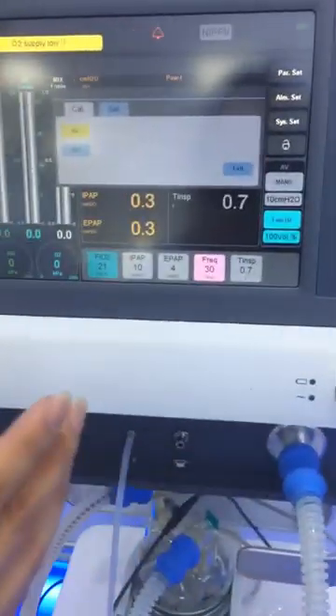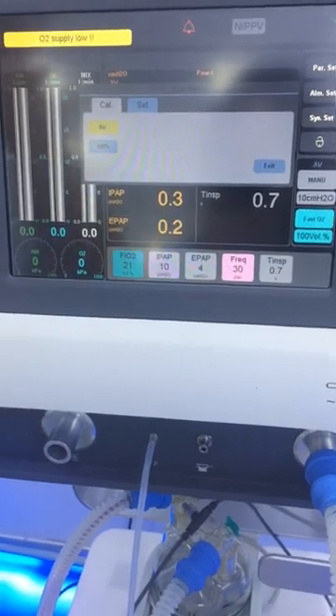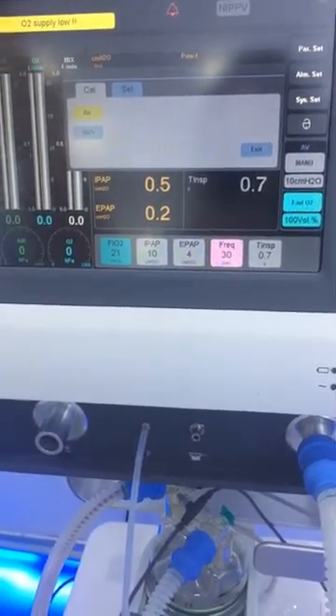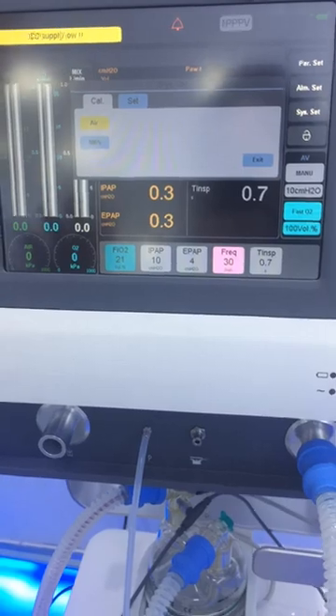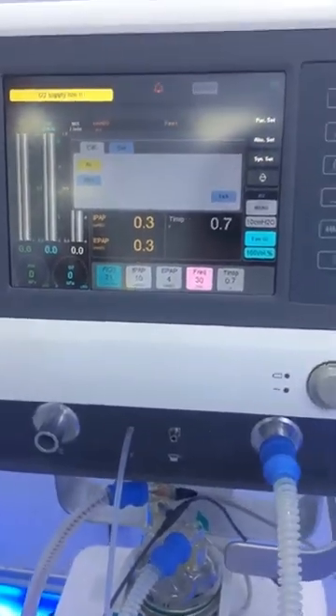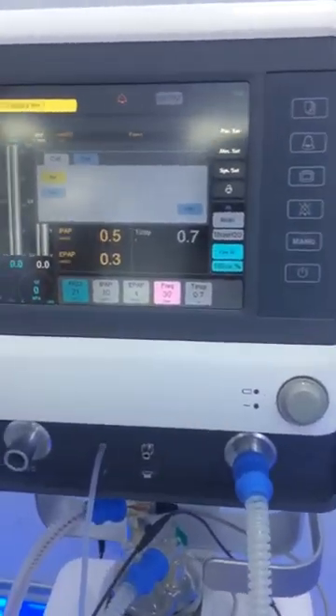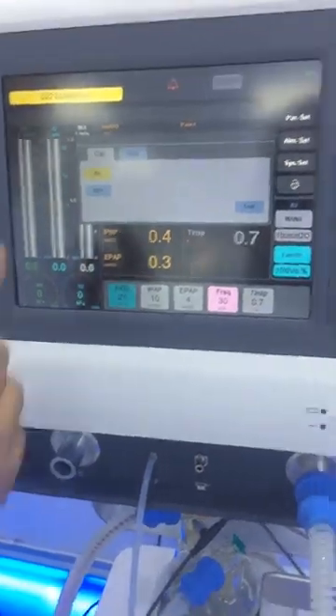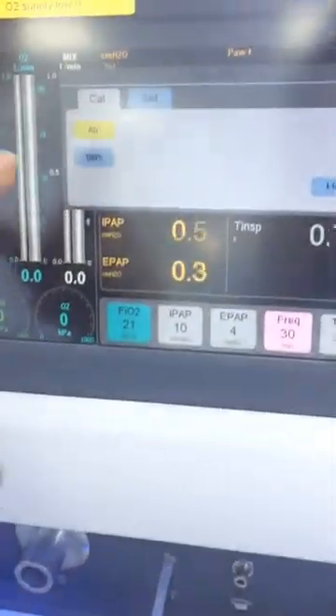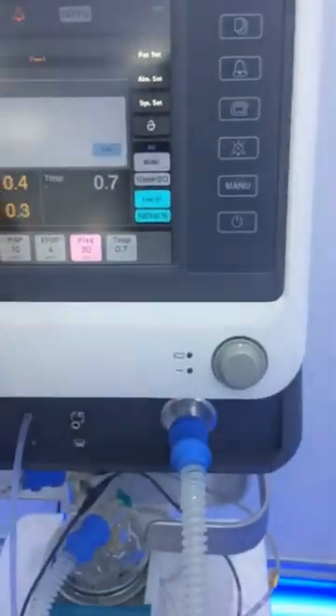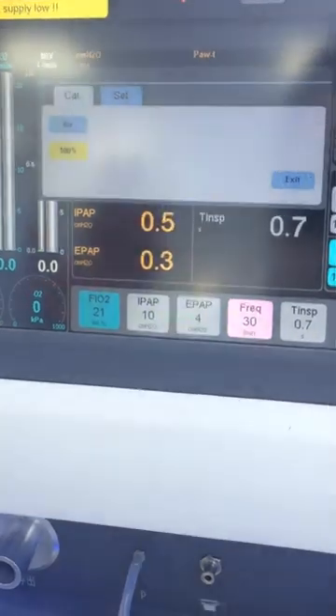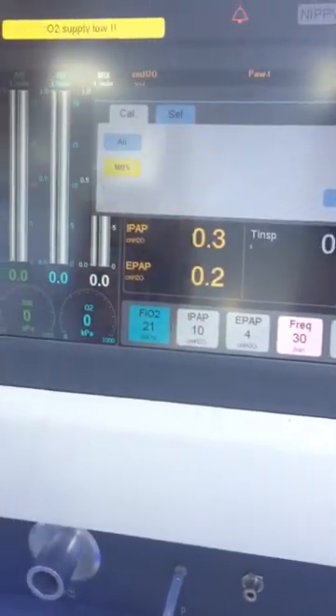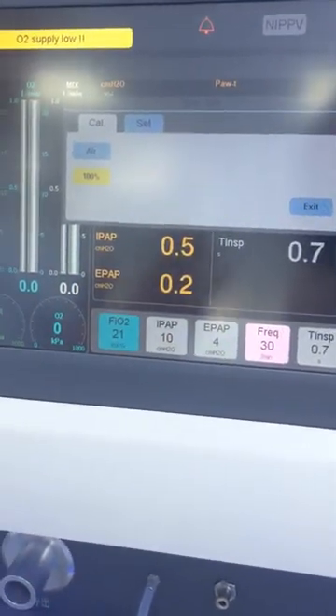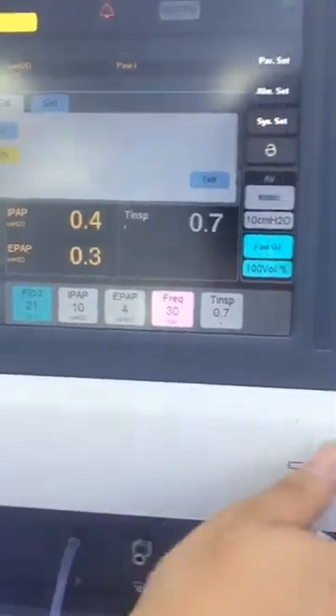The third one is the system setting. Under the system setting here, because we are using the electronic flow meter, we only need to adjust the air and 100% oxygen directly. For the air, we just press it, and after it's complete, it's finished. For the pure oxygen, it's the same. The only thing you need to remember is that when we are doing the oxygen calibration, you must ensure only oxygen is coming, no air coming.